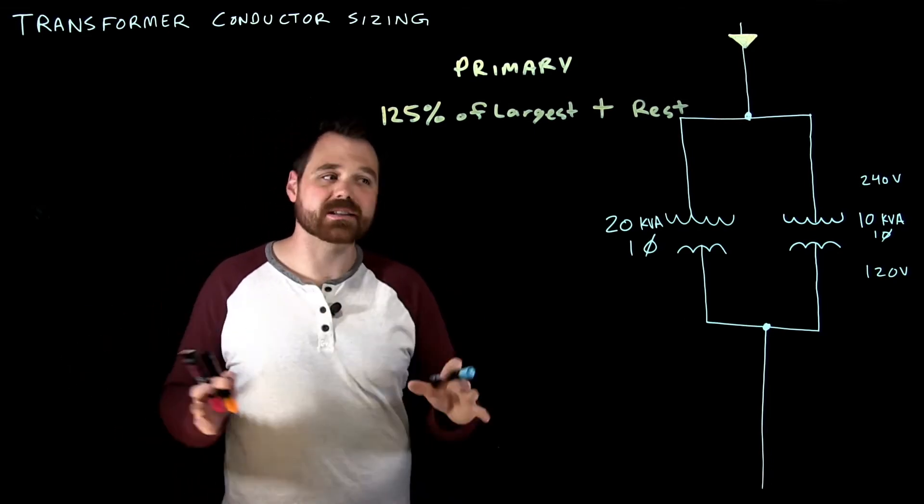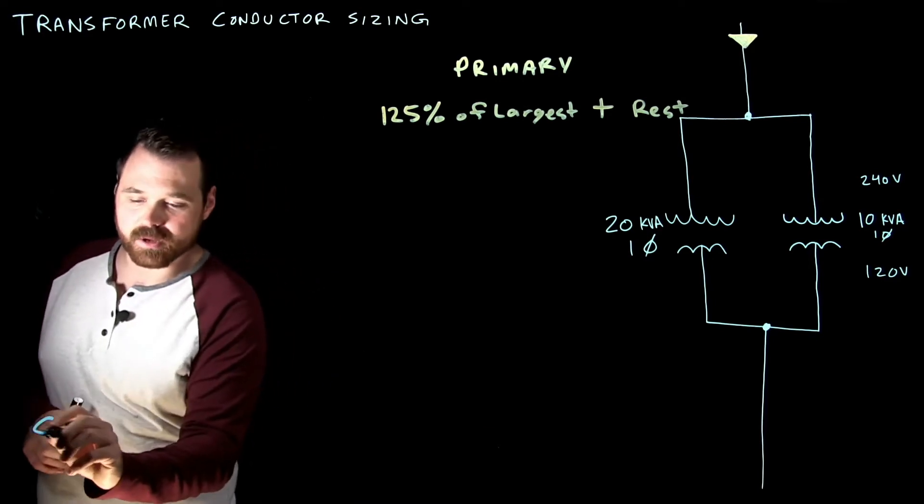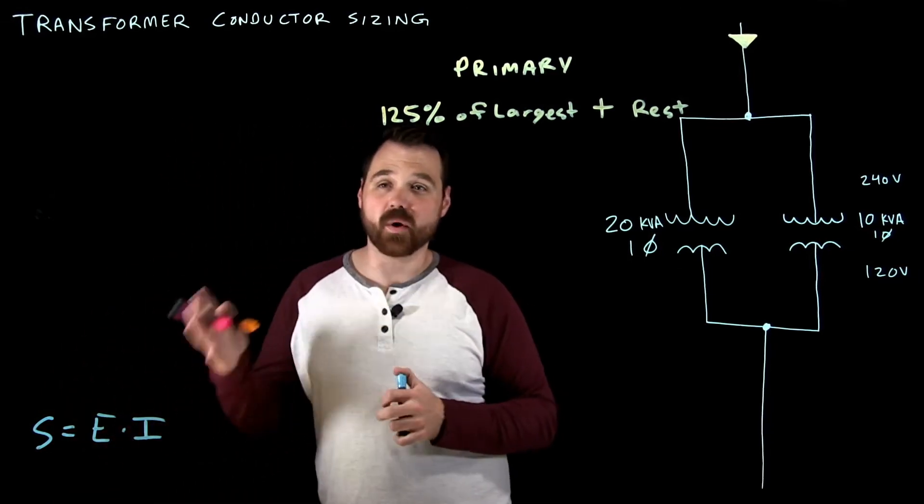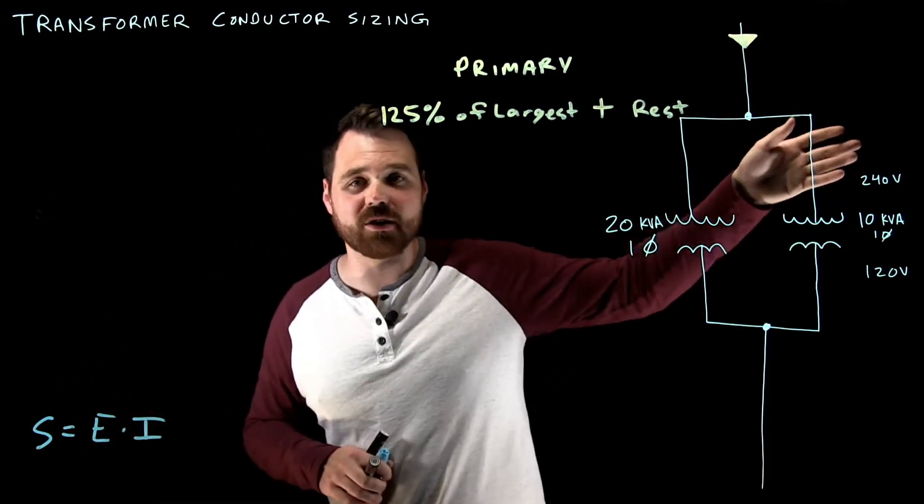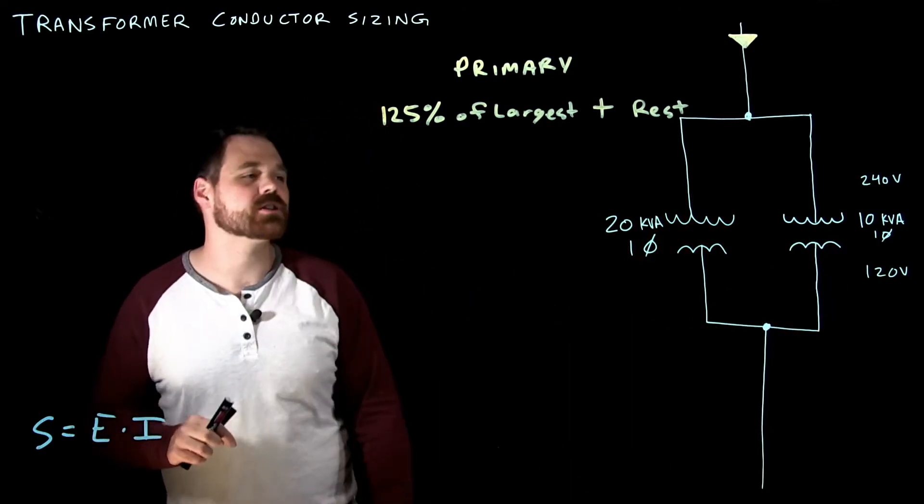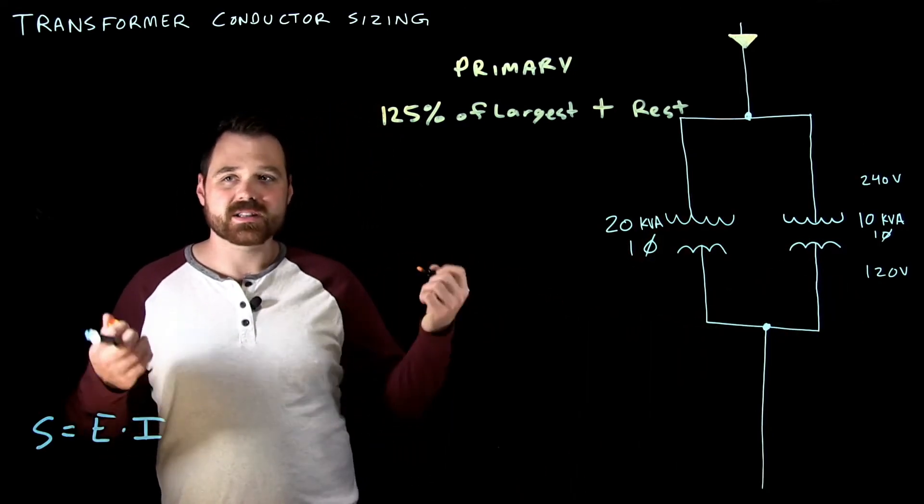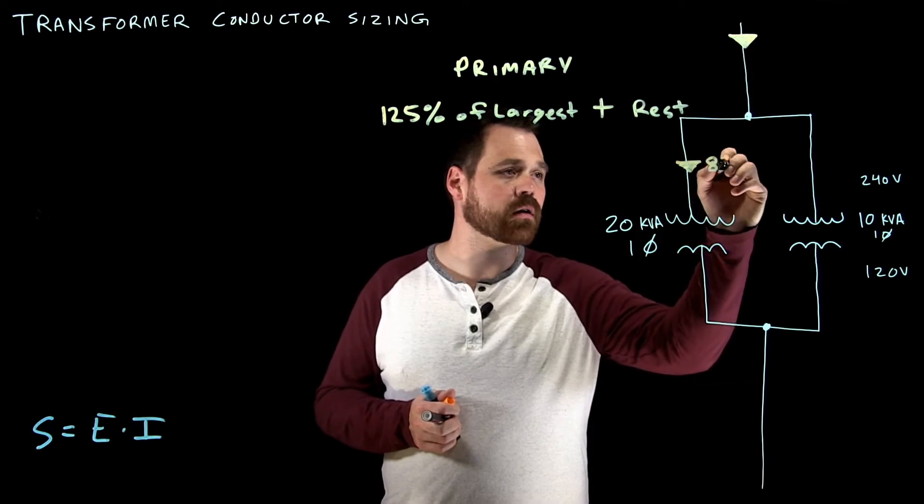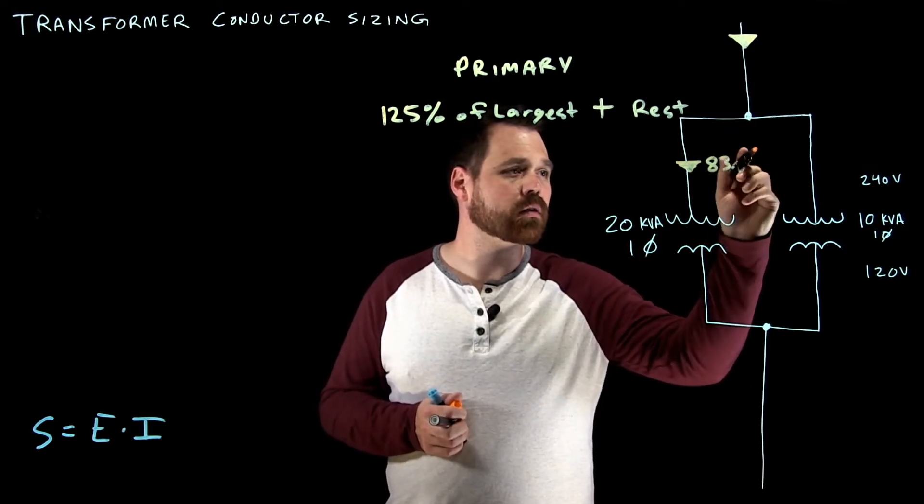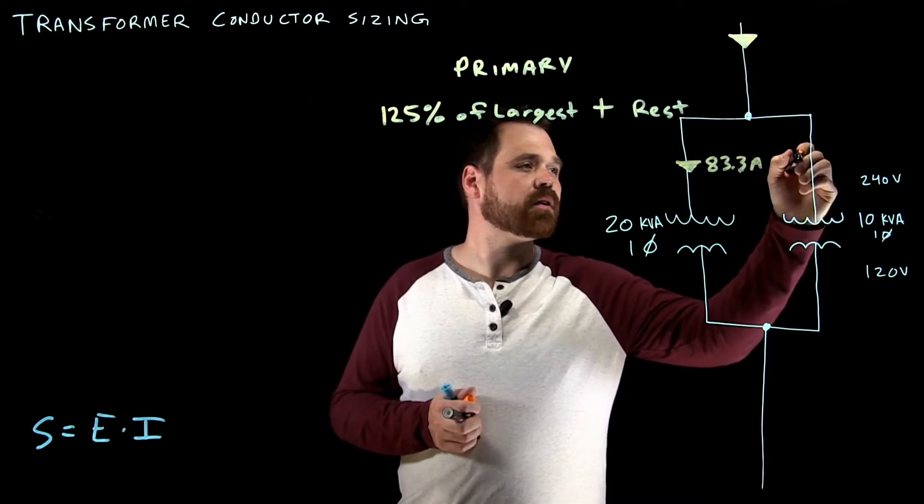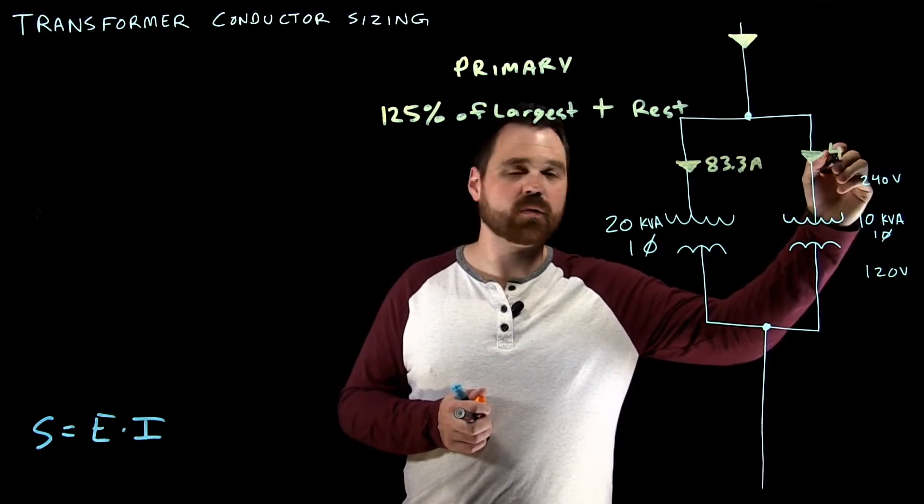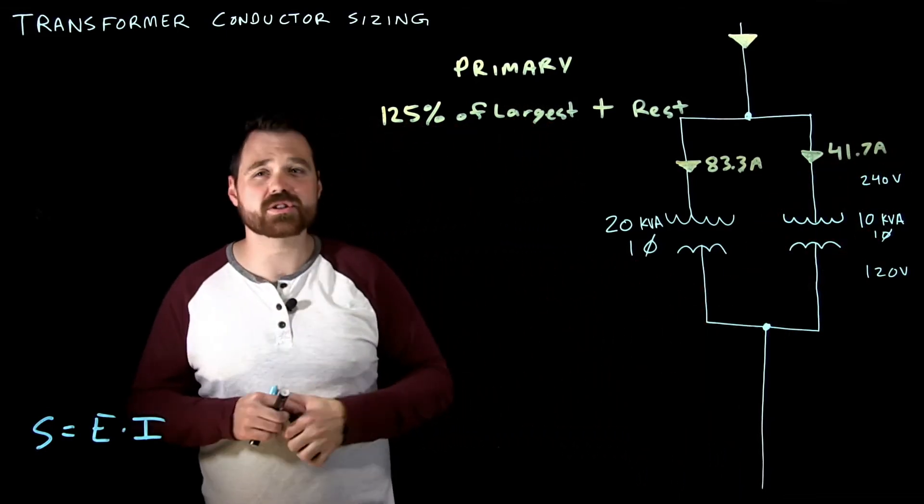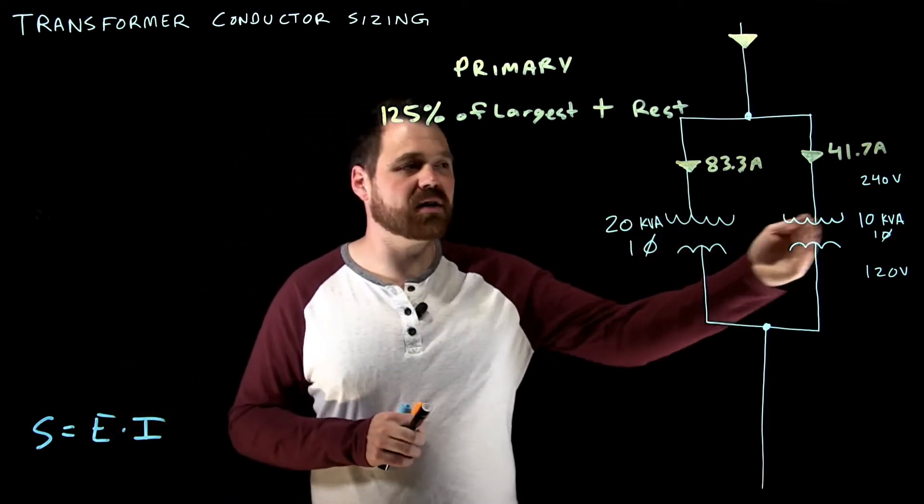So in this case, because I'm dealing with single phase transformers, now I'm going to take that formula S equals E times I, knowing my voltage on my transformer, it's a 240 volt primary, and a 120 volt secondary, so new voltages as well, I can figure out my rated current. So now in this case, I've done the math. On this transformer, I get 83.3 amps. And on this transformer, I get 41.7 amps. So those are the rated primary currents of the individual transformers.